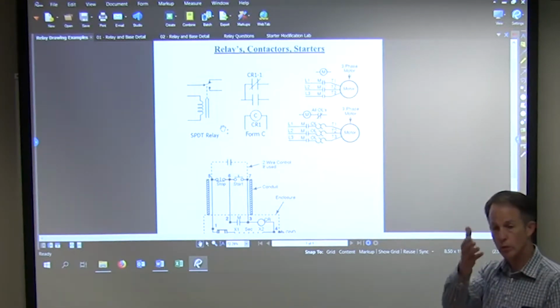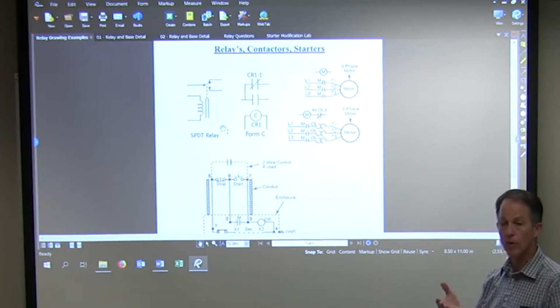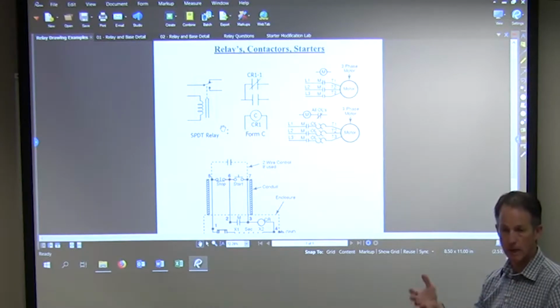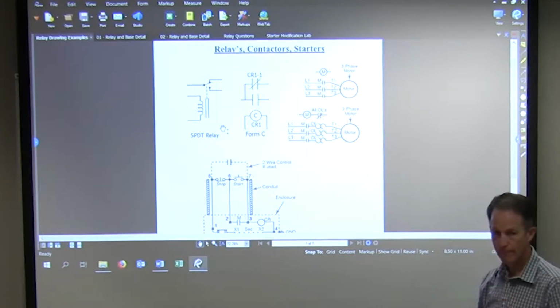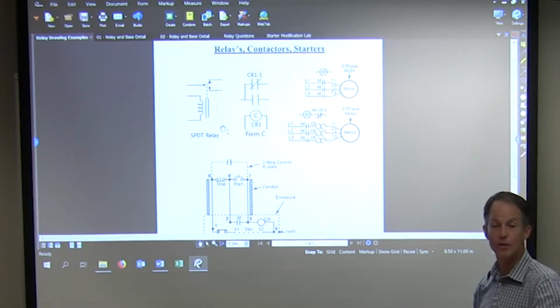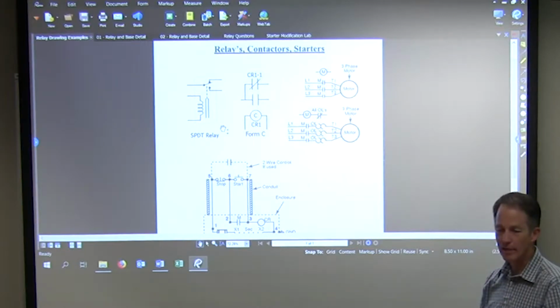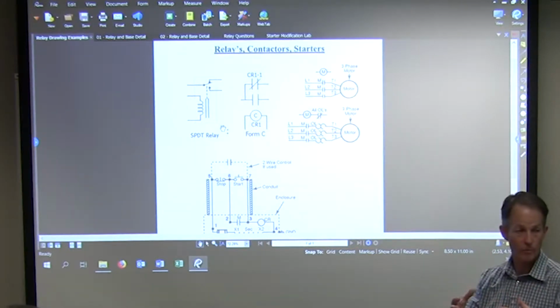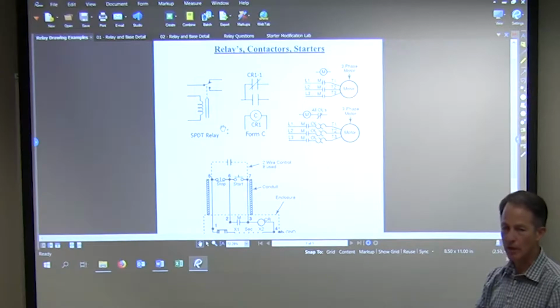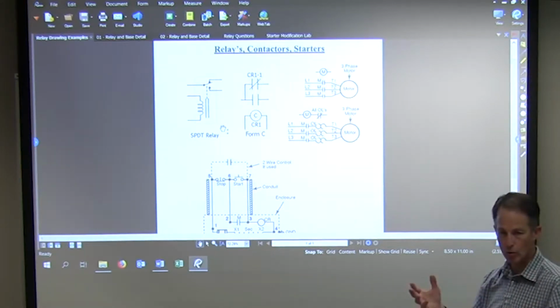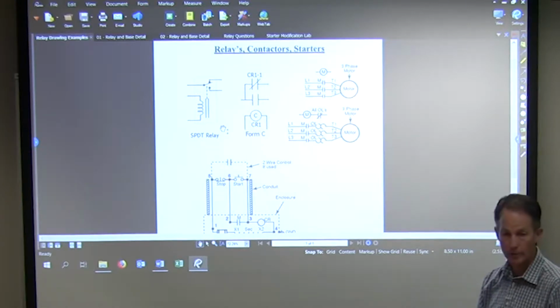Okay, so which would you start with? Right, voltage. Yes, voltage, because typically it's in a circuit that's powered. Not always, but a lot of times. So if I put it on voltage, what type of voltage, AC or DC? Whatever it calls for. Okay, what is it calling for? On the coil? Well, it depends on the circuit. If the circuit is one that we know has a 24 volt transformer, 120 volt, we're probably going to be AC. We'll start there, and very rarely do you see a DC circuit in the control world, but we do have it. We have 0 to 10 outputs, and sometimes we'll use those outputs to switch on a relay that has a DC coil. Not very often, but sometimes.